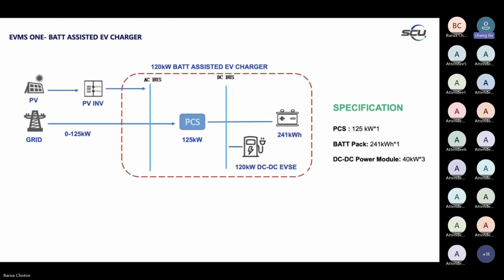So the grid takes from 0 to 125 kilowatt, and it connects to the AC bus. Then the AC comes to the PCS, and after the PCS, it's all DC. So we have a DC bus, then the battery is connected to the DC bus. And because we're using the DC-DC power module in the EV charger, that's a DC-DC EV charger of 120 kilowatt, connected to the DC bus bar.